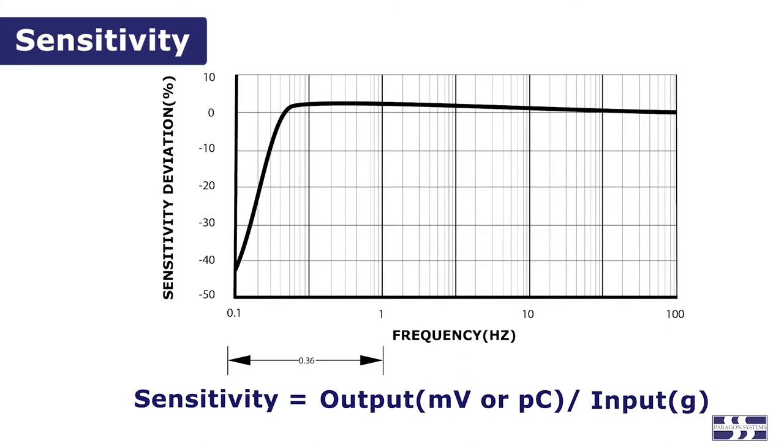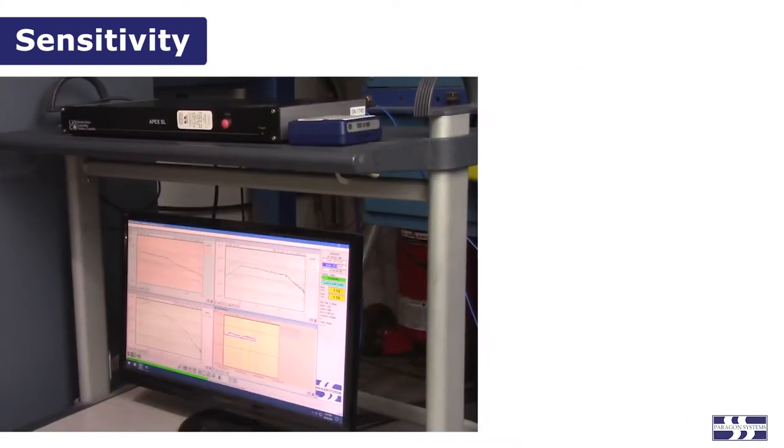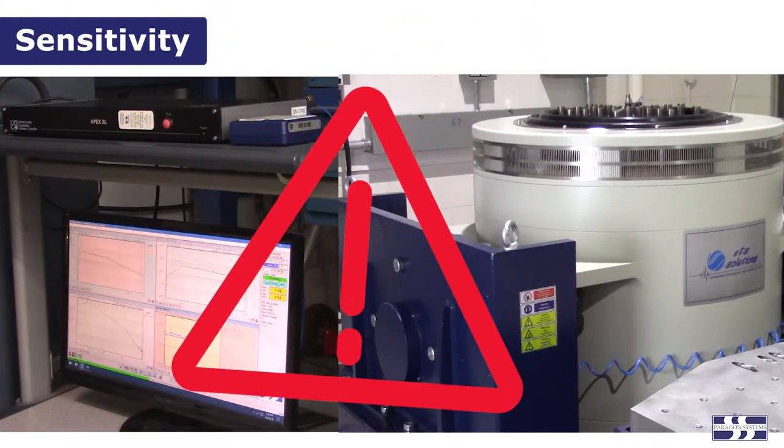If you're performing a test at a low level, for instance like 0.25 Gs RMS, it's necessary to select an accelerometer that has a high sensitivity, otherwise the controller will not receive a signal higher than the background electrical noise and will be unable to control the shaker.